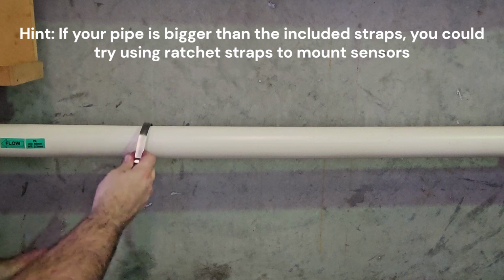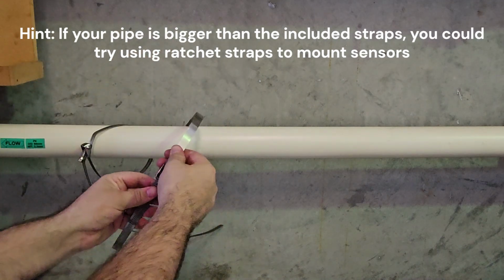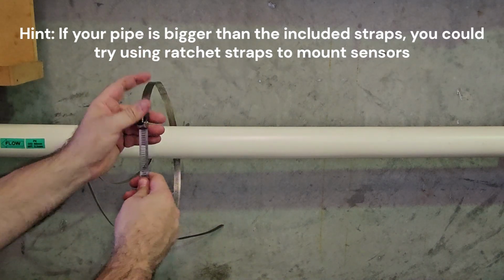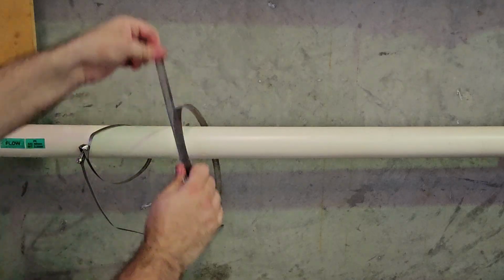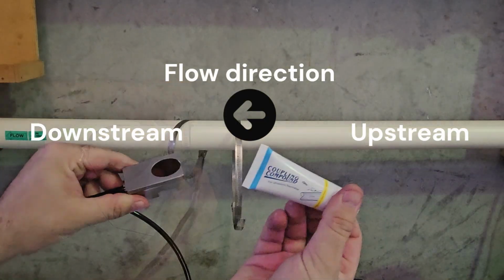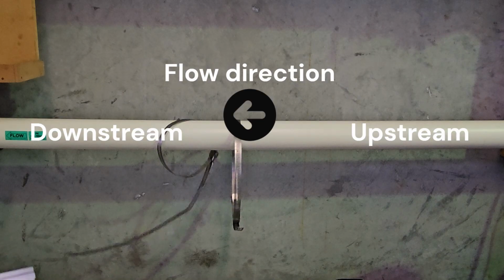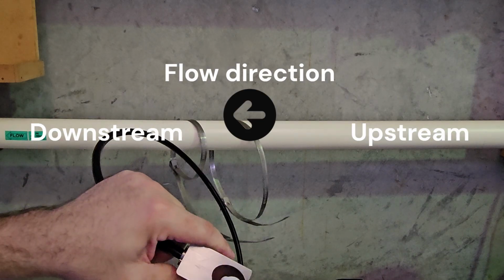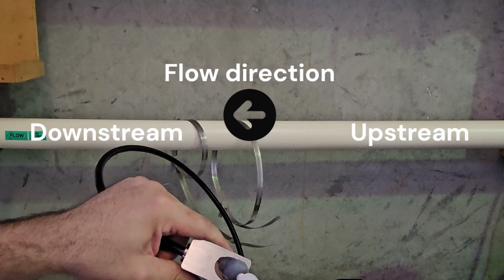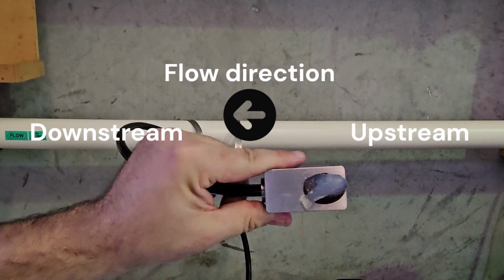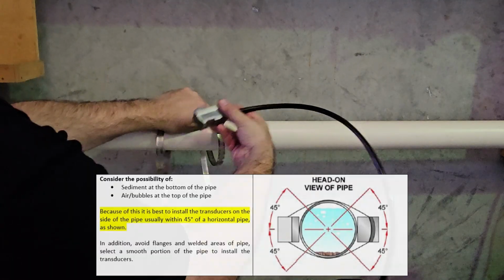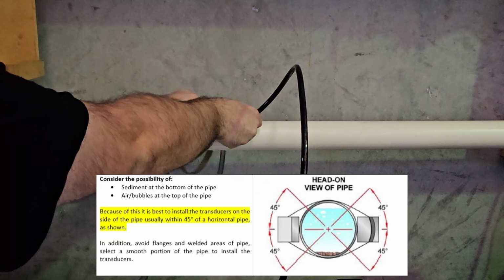You can set them so they are just a little bit wider than required, so the sensor just fits between the strap and the pipe. I am first installing the upstream sensor. Take some couplant and apply a blob on the sensor surface. Use enough to cover the brown oval once it's squished onto the pipe. Now, noting the flow direction, place the sensor onto the pipe and slide the strap over and tighten it down.